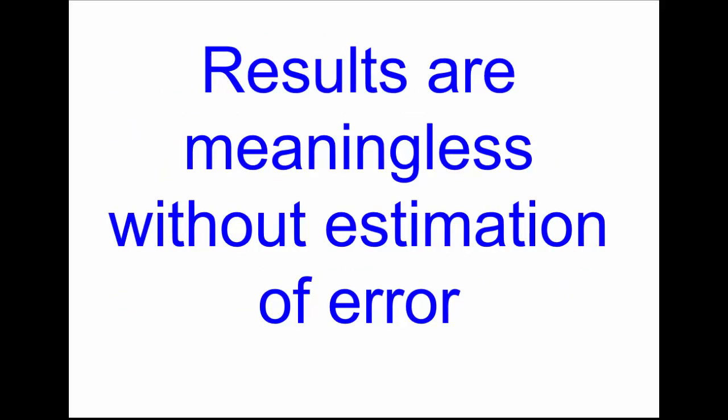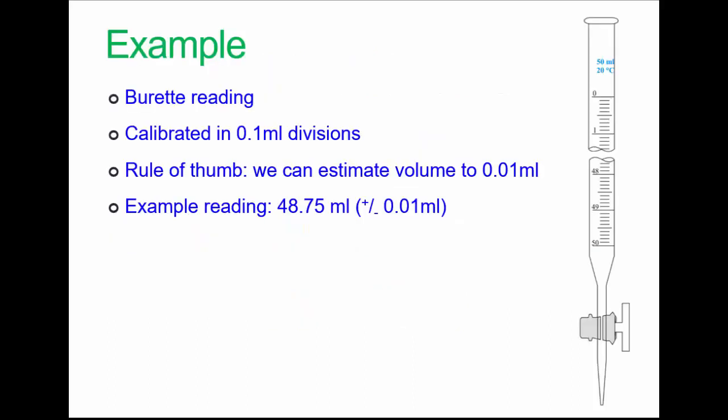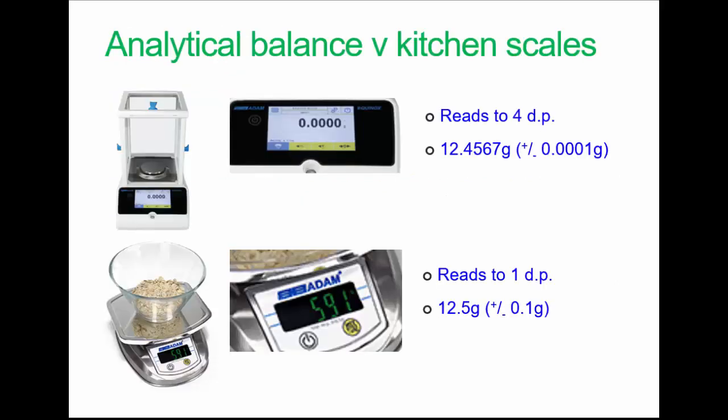Here's a key thing which is important when you're reporting results: results are meaningless without an estimation of error. Here's a burette. It's a 50 ml burette calibrated in 0.1 ml divisions. A good analyst can estimate the volume down to 0.01 mils. In practice, maybe 0.05 ml will be what most people could do. A good analyst would quote results as: my reading was 48.75 plus or minus 0.01 ml. How much this would be depends on the equipment. This can be very much higher or lower depending on the type of technique you're using.